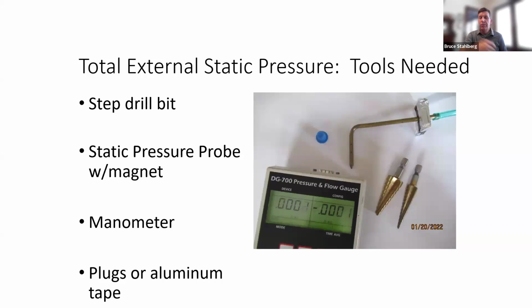What kind of tools do you need for doing static pressure? Well, we need a step drill bit. Those 2 bits there are called step drill bits. The reason that's important is you'll notice they have little intervals, so we only go in a little bit at a time. That helps you control how far you're going in. I would never, ever use a regular drill bit, because once you go through the metal, it can pull that drill bit into the cavity and you might hit an air conditioning coil or heat exchanger. So don't use that type of drill bit.